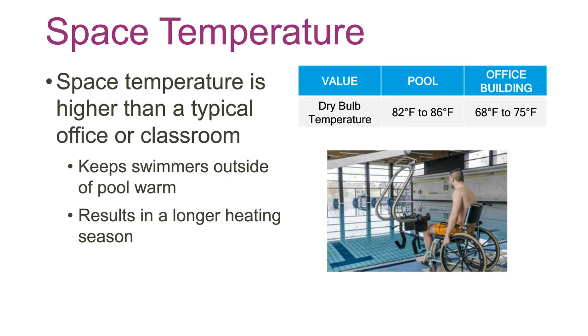So I mentioned the high dew point. Well, space temperatures in a natatorium are usually 82 for a competition pool-ish to 86 oftentimes for a rec pool. So you're 10 degrees warmer than what you're doing with a normal space, and that's because the occupants in large part just have swimsuits on, so they need to be kept warm. It results in a heating season that's typically 3 months longer than people think about when they're designing spaces. So a pool application is largely in heating 9 to 10 months out of the year, almost in any climate.